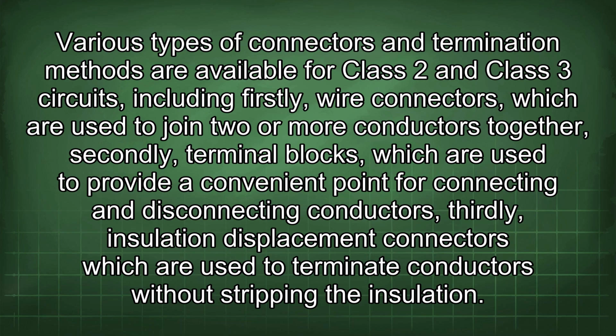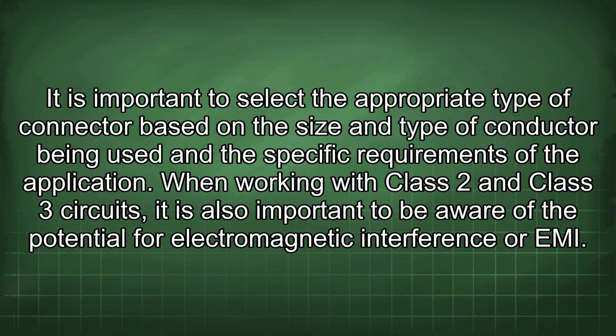Various types of connectors and termination methods are available for Class 2 and Class 3 circuits, including, firstly, wire connectors, which are used to join two or more conductors together. Secondly, terminal blocks, which are used to provide a convenient point for connecting and disconnecting conductors. Thirdly, insulation displacement connectors, which are used to terminate conductors without stripping the insulation. It is important to select the appropriate type of connector based on the size and type of conductor being used and the specific requirements of the application.